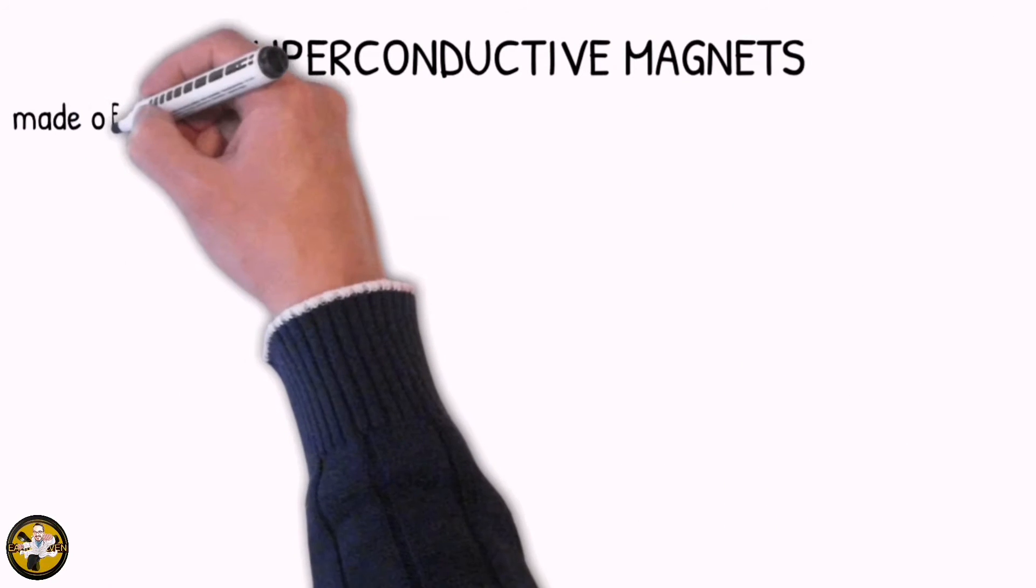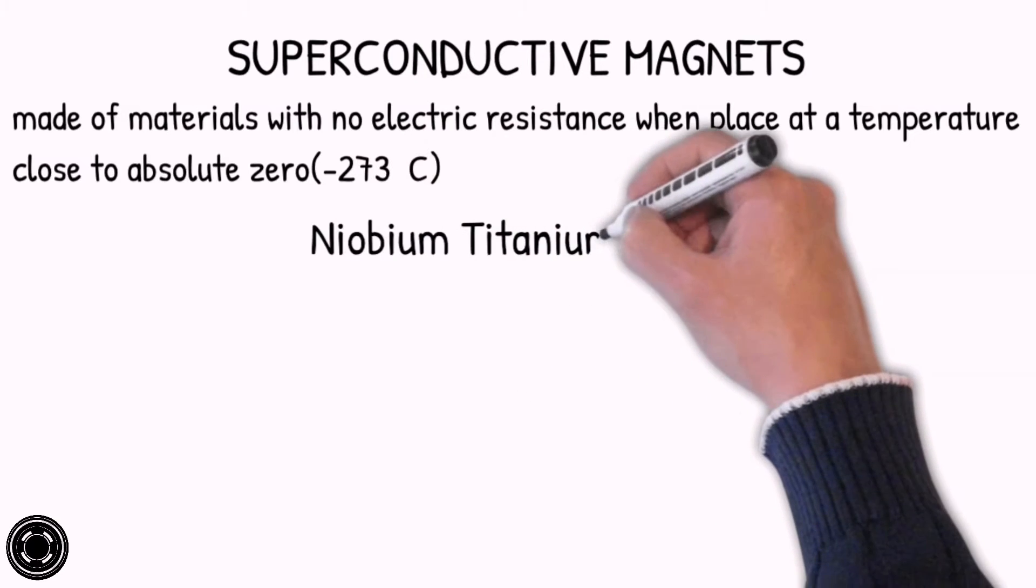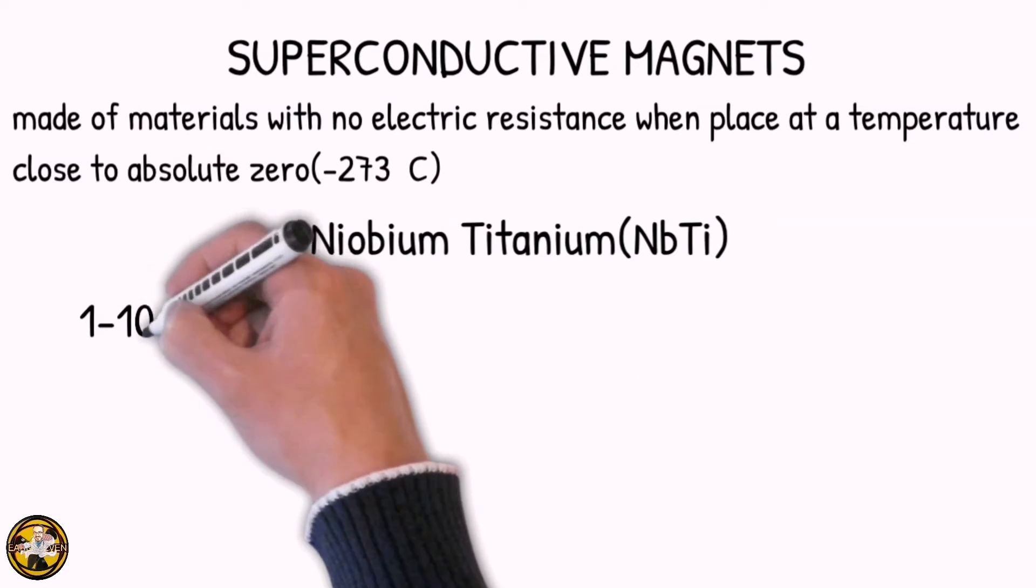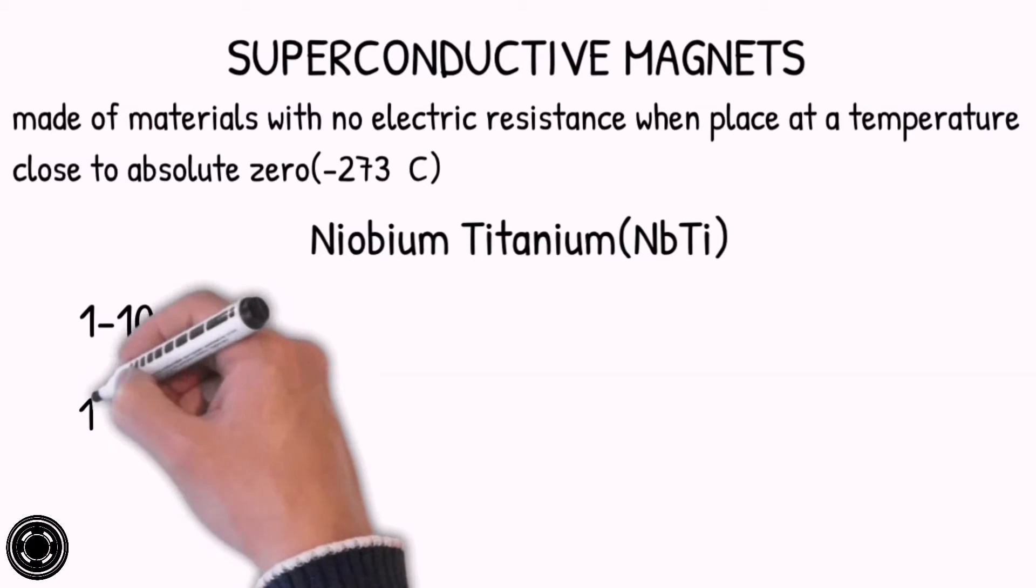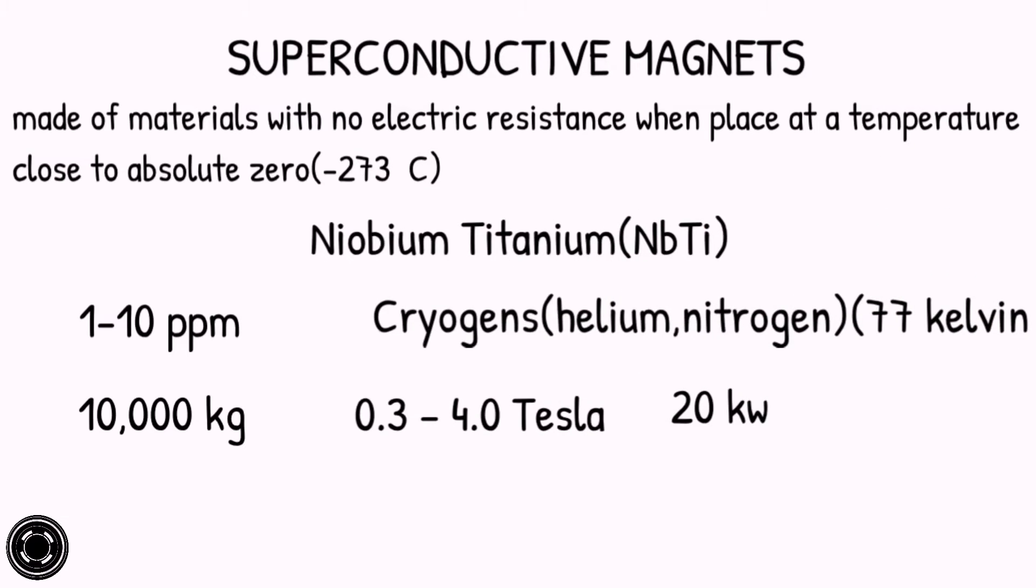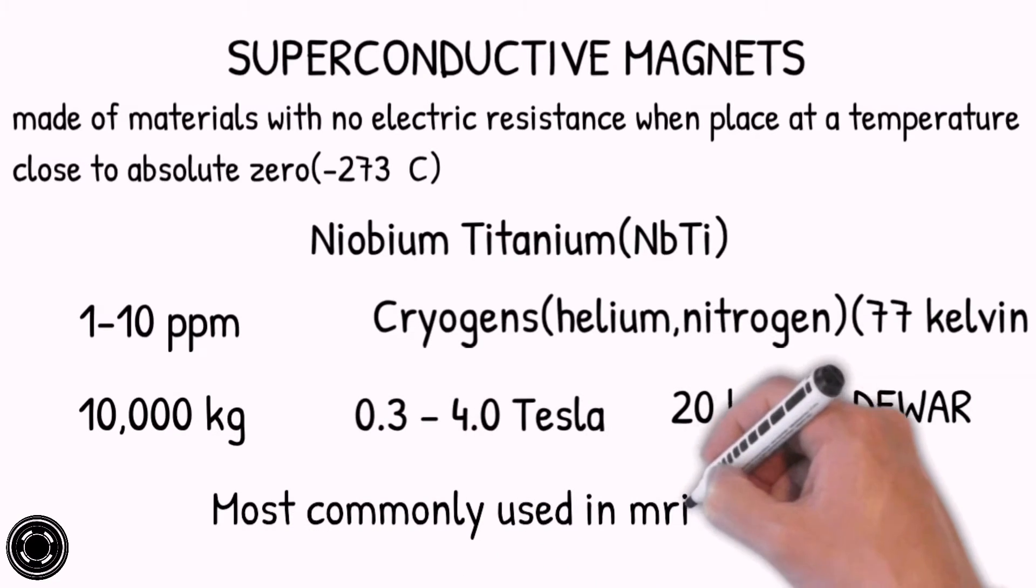The third type of magnet is the superconductive magnet. It is made of materials with no electric resistance when placed at a temperature close to absolute zero. Niobium titanium is the metal used. Magnetic field homogeneity is 1 to 10 ppm, weight is approximately 10,000 kilograms, magnetic field strength is 0.3 to 4.0 Tesla, power consumption is 20 kilowatts. The cooling system used is the cryogen composed of helium and nitrogen, and it is enclosed within a giant container called the dewar. It is the most commonly used in MRI systems.